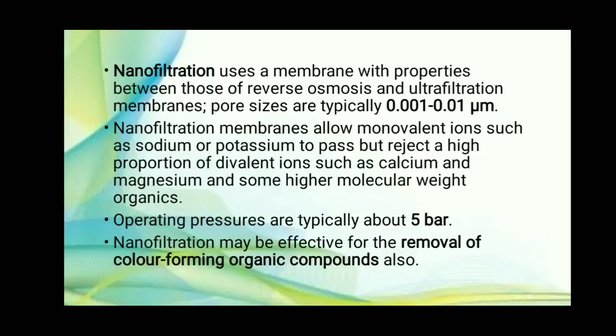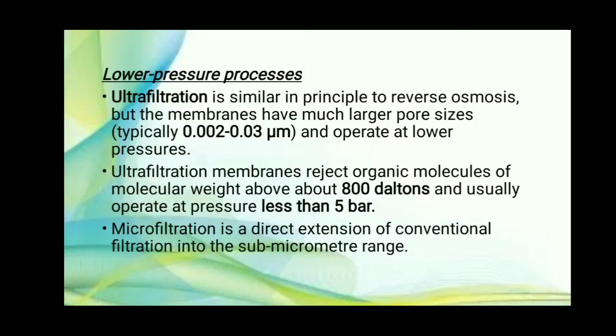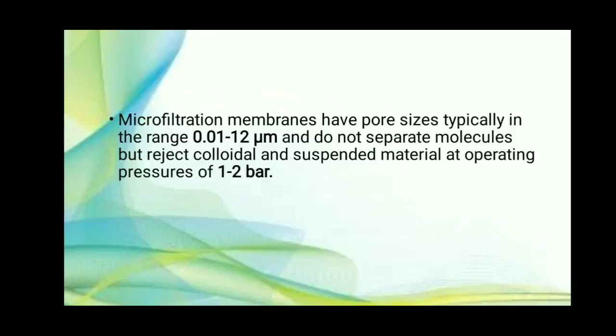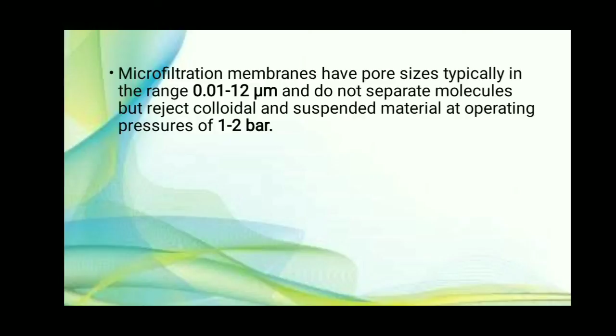Then the lower pressure process is ultrafiltration. It is similar to reverse osmosis, but the membrane pore size is about 0.002 to 0.03 micrometer, and it requires lower pressure, that is less than 5 bar. It rejects molecules of weight above 800 daltons. Microfiltration is the direct extension of conventional filtration into the sub-micrometer range. In microfiltration membranes, pore size is 0.01 to 12 micrometer and the pressure required is 1 to 2 bar.